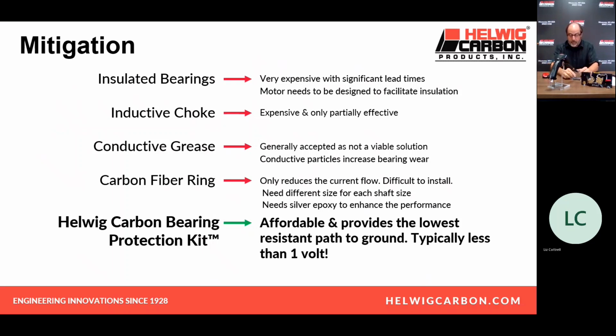And it works very well, and very good at high frequency. It works very well at high frequency. That's why we use silver graphite, and we don't paint silver on the shaft. We simply put the silver in our kit. Gotta have silver to be effective. We embed it into our kit. We do not paint it on the shaft. Therefore, we have no maintenance. Once we're installed, you never have to take us off, paint colloidal silver on the shaft, ever. When we're in, we're done.